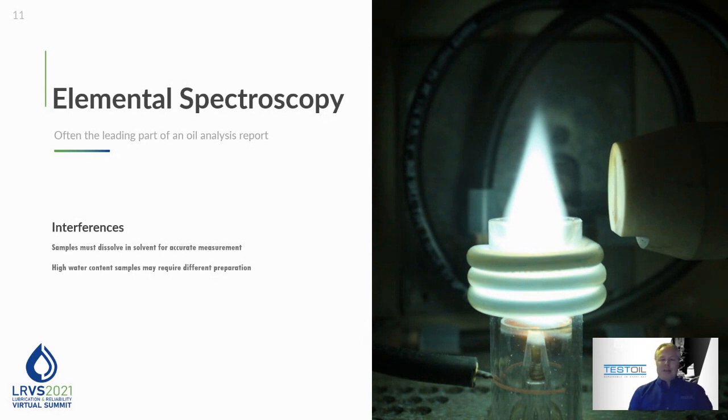But the joke I always make about this is if you've got so much water in your sample that we can't get an accurate elemental spectroscopy, there's your problem. High water content. Don't worry about what your wear metals are doing until you get rid of the water.